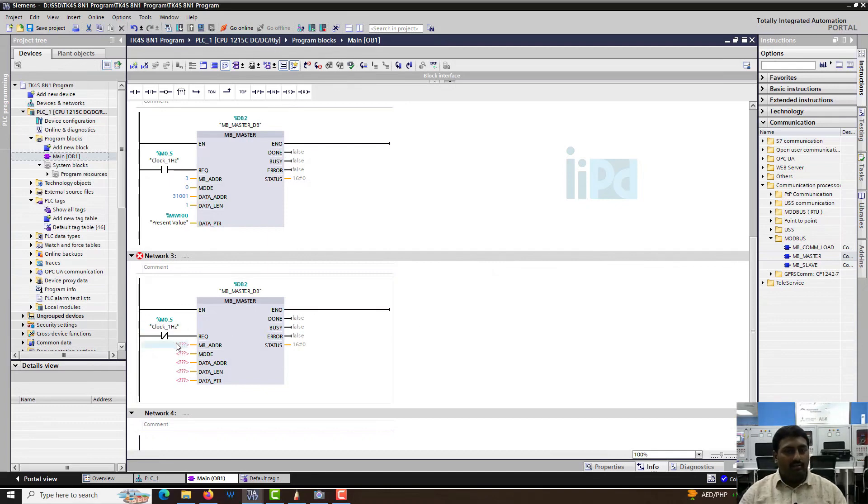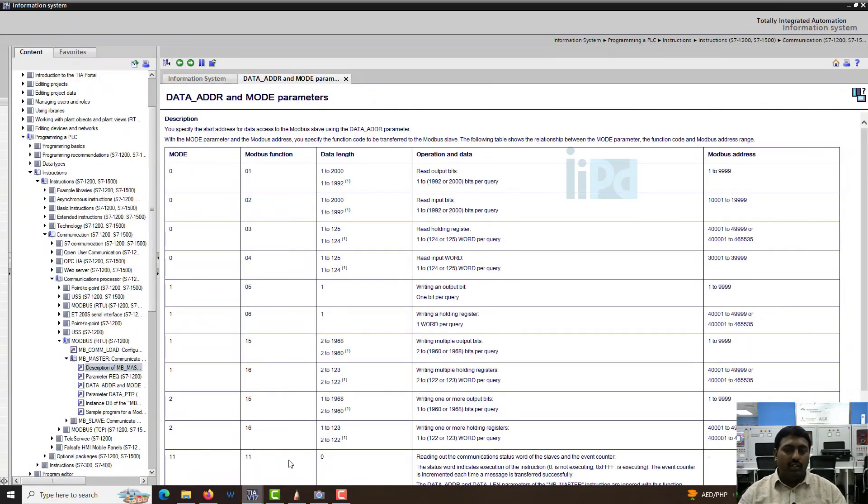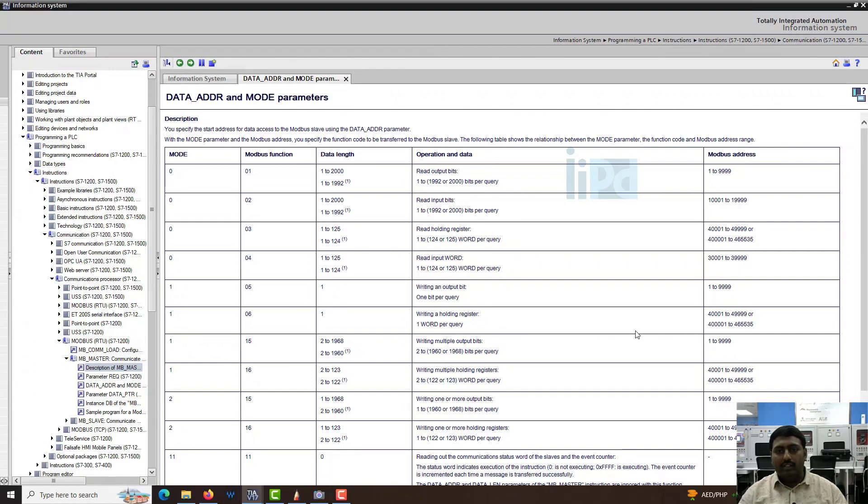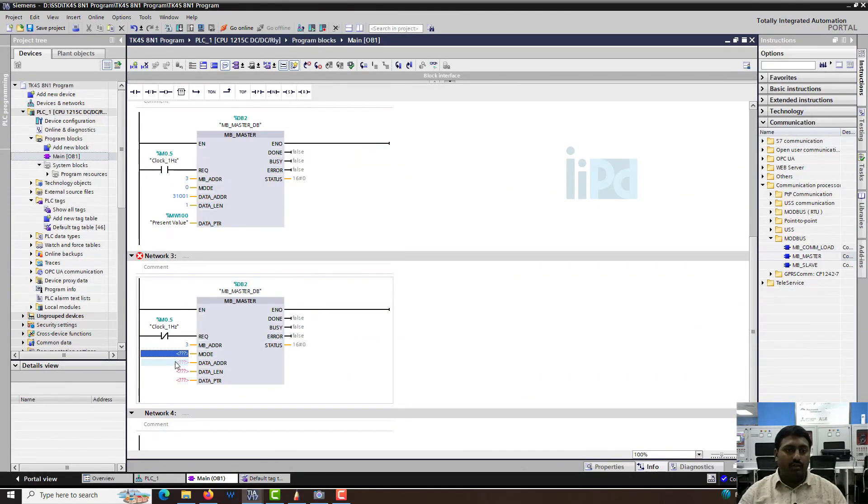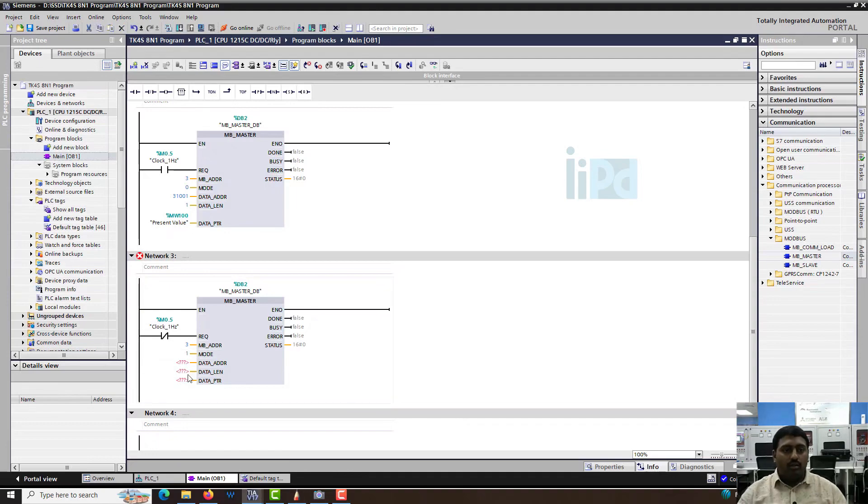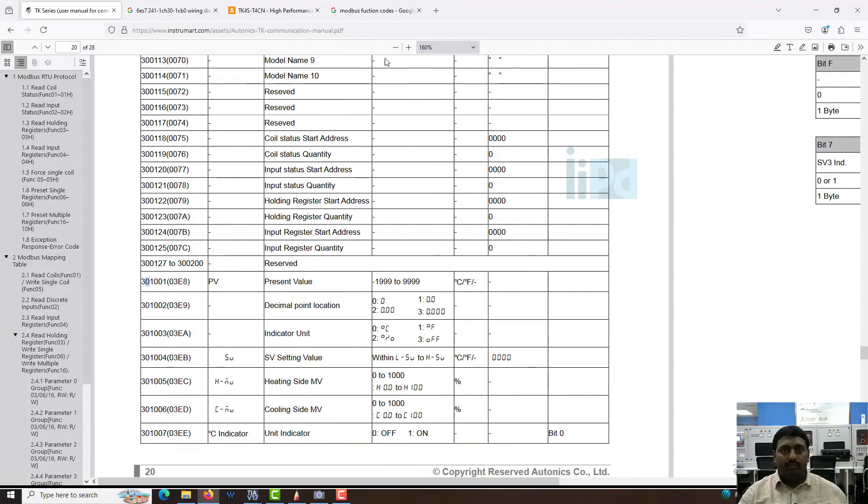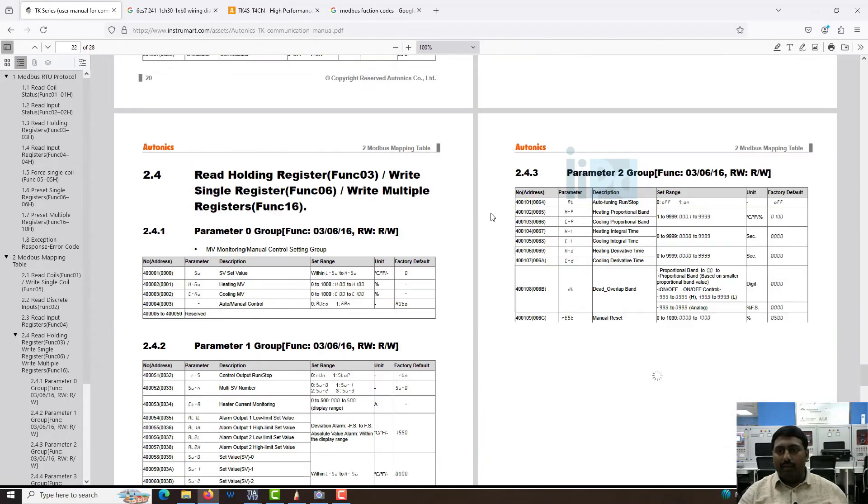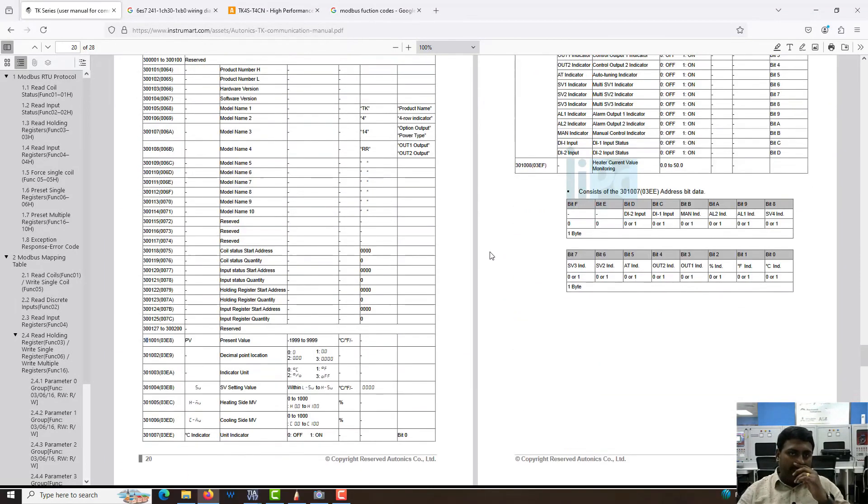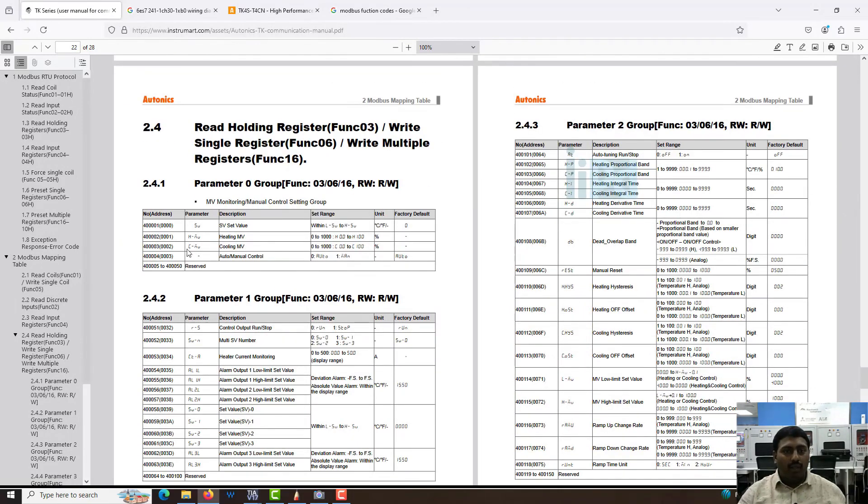Now the mb address again, we are going to write to the same device. The mode is changed because we are going to write a value. Writing to a holding register, one or multiple registers, the function code with mode one. We need to know where to write the data. The three registers are all only input registers, we cannot write to it. Obviously, the data to write will be in the four register.